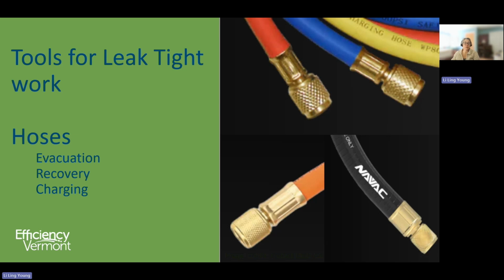And I think that's really important because one of the things that pushes technicians to take shortcuts is slow moving processes. If it's taking half an hour to reach a deep vacuum on a new system, some technicians are tempted to get it to 800 microns, watch it for a minute, and then call it good. And that is not the way to make a leak-free, long-lasting system. Deep vacuum and a vacuum decay test is best practice.